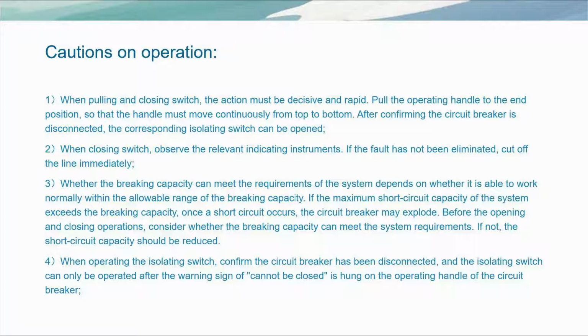3. Whether the breaking capacity can meet the requirements of the system depends on whether it is able to work normally, within the allowable range of the breaking capacity. If the maximum short circuit capacity of the system exceeds the breaking capacity, once a short circuit occurs, the circuit breaker may explode. Before the opening and closing operations, consider whether the breaking capacity can meet the system requirements. If not, the short circuit capacity should be reduced.